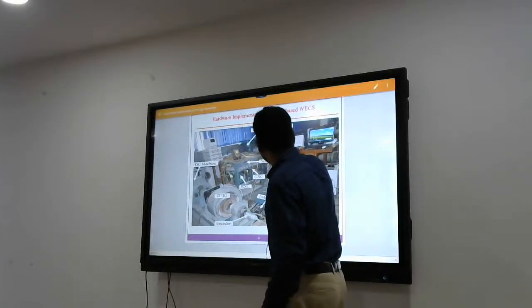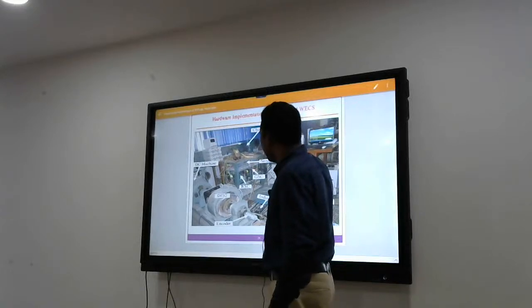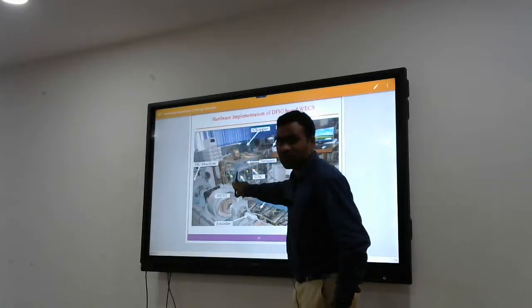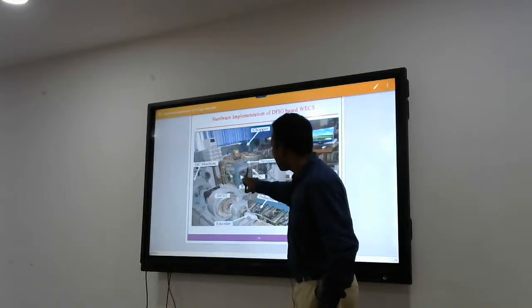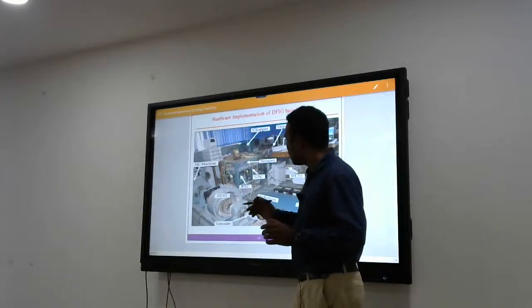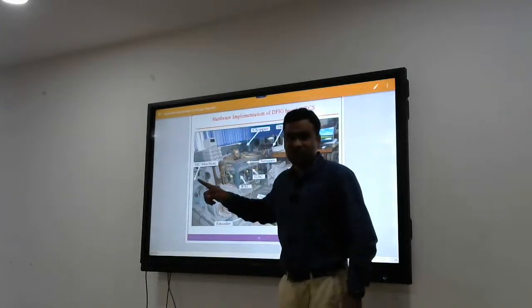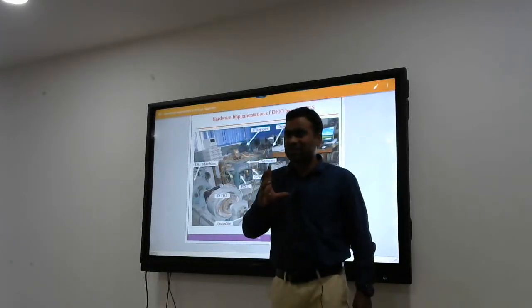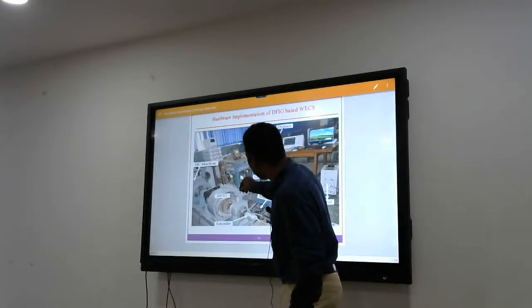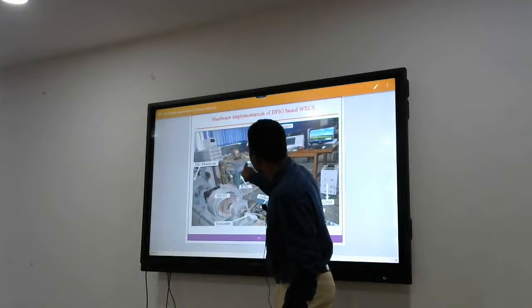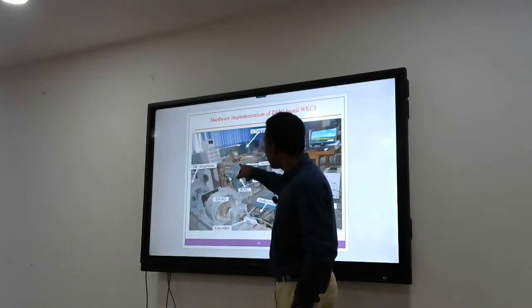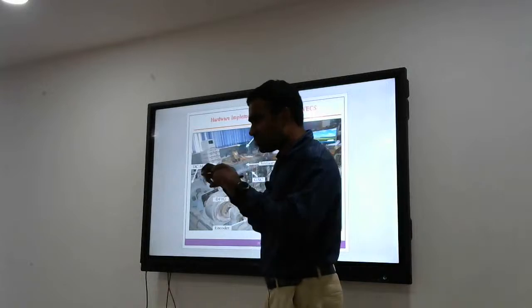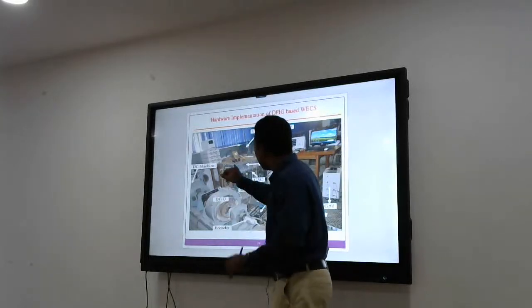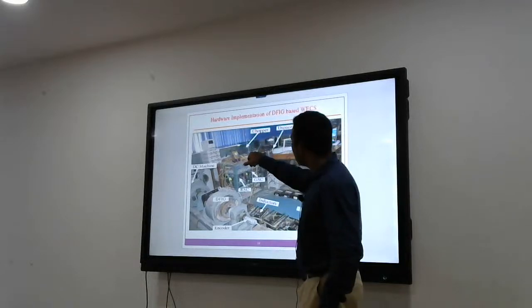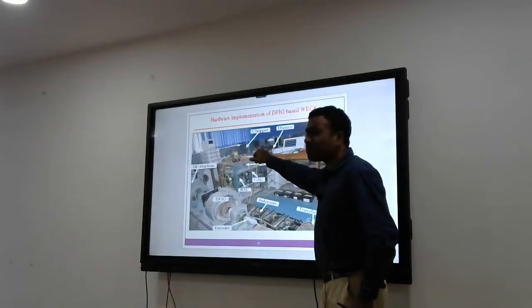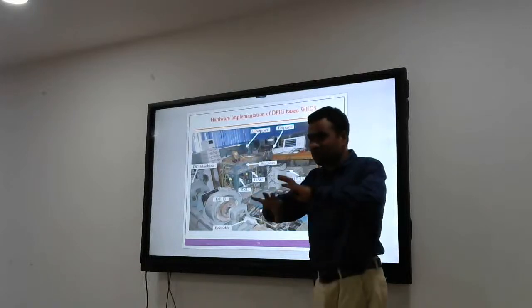Yes, this is the dSPACE. This is the controller that is controlling everything. Here, these are the two converters I told you about, the rotor side converter and the grid side converter. These are the two converters, or otherwise you can call them inverters. Here you have all the sensors. I think you need 15 to 20 sensors to sense different voltages and currents. You normally take the wire from here and sense here. After sensing, you have to prepare signal conditioning circuits on your own, those boards and PCBs, and from there you give the signal to the microcontroller or digital signal processor. It will do some computing inside.